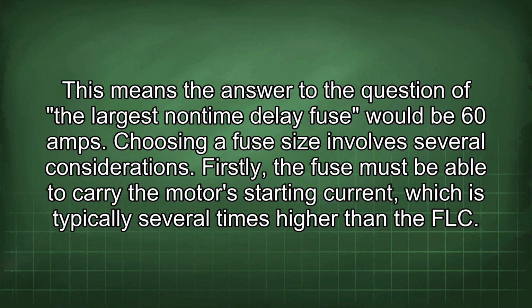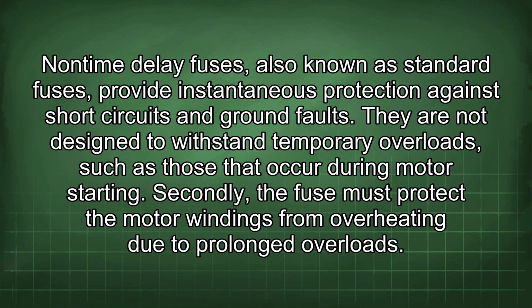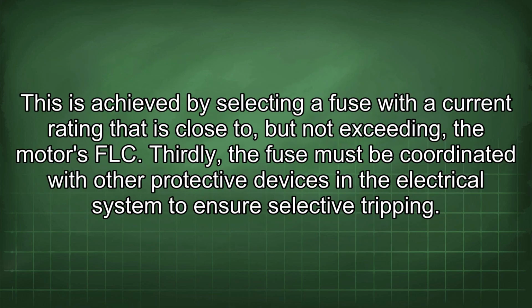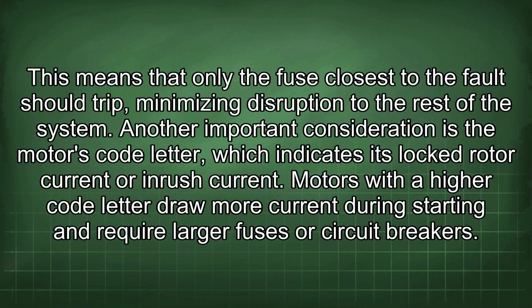Choosing a fuse size involves several considerations. Firstly, the fuse must be able to carry the motor's starting current, which is typically several times higher than the FLC. Non-time delay fuses, also known as standard fuses, provide instantaneous protection against short circuits and ground faults. They are not designed to withstand temporary overloads, such as those that occur during motor starting. Secondly, the fuse must protect the motor windings from overheating due to prolonged overloads. This is achieved by selecting a fuse with a current rating that is close to, but not exceeding, the motor's FLC. Thirdly, the fuse must be coordinated with other protective devices in the electrical system to ensure selective tripping. This means that only the fuse closest to the fault should trip, minimizing disruption to the rest of the system.